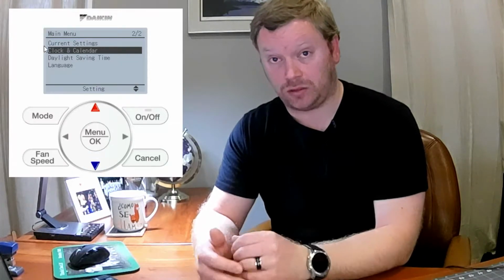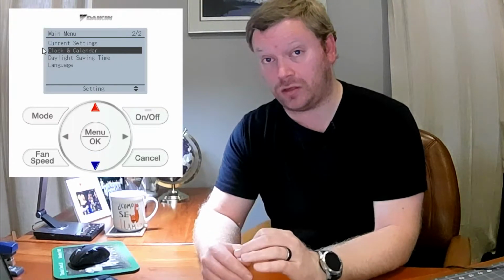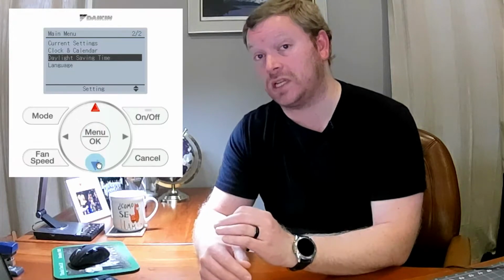So to set the clock, you're actually going to go down from the main menu into the second page, and you'll see your clock settings. Now, before you set your clock, I recommend that you set daylight savings time first. If you set the clock and then you set daylight savings time, and we're currently in daylight savings time, when you go back to the main screen, you're going to be an hour ahead of what you should be. So do the daylight savings time first, and then set the clock.